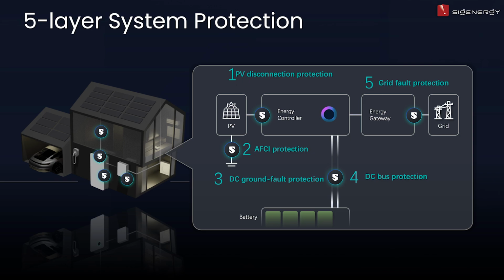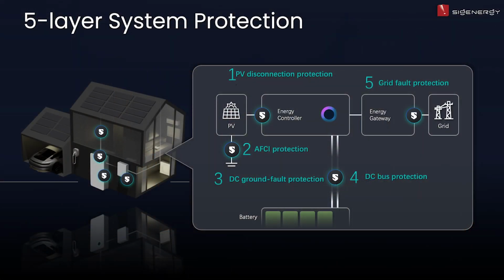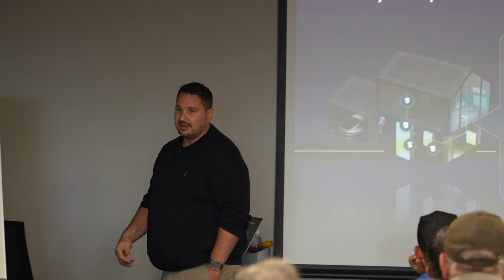All right, then on the system side, there is also 5-layer protection, which is PV disconnect protection. It does have it built in, okay? It's got arc fault protection built in. It's got DC ground fault protection built in to make sure that if there's any leakages to earth, that it's there. It's got a DC bus protection on the battery side, so to make sure that there's no overcurrents and over voltages flowing in. And then it's got grid fault protection built in. So if there's any grid failures or anything like that, that it islands off. So it's got an isolator and a fuse on the inside. It's got an isolator and a fuse in here, and it does have earth leakage protection in there. So no need for anything because it's all built in to the system.